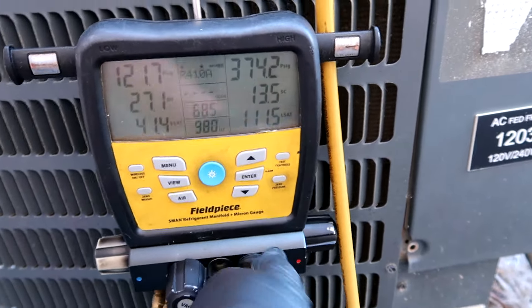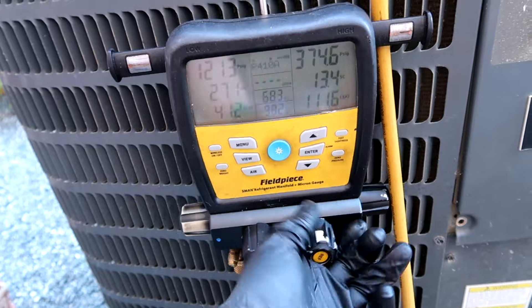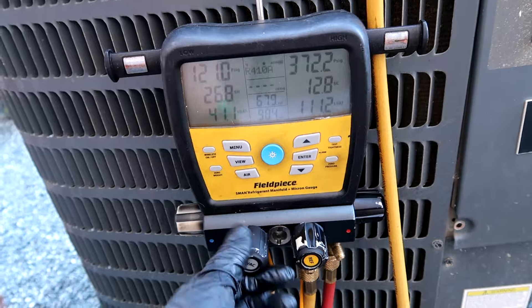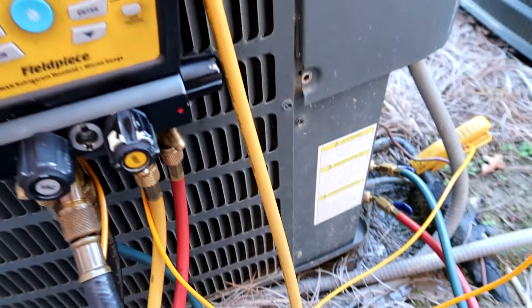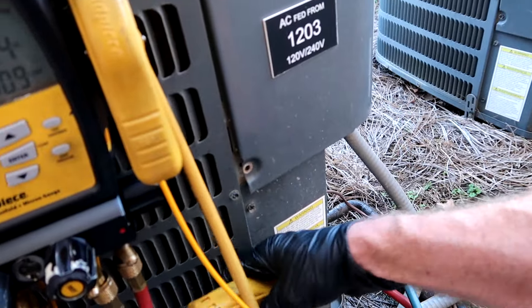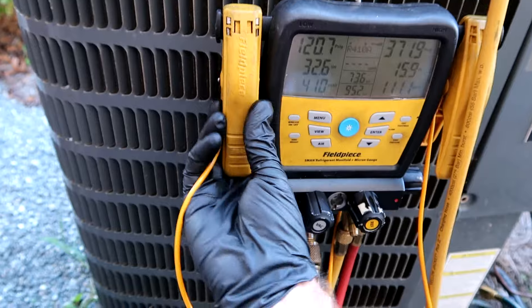Close up my stuff here — it's got a leak in it anyway. Like I said, they're all leaking and the squeaky wheel gets the grease, meaning if they complain a lot or we have to be there filling up with refrigerant every month, that's when we'll snatch the coil out and put in a new one. But now my new ones are leaking — I put one in two years ago and it's leaking. You go tell somebody and they just say don't worry about it.